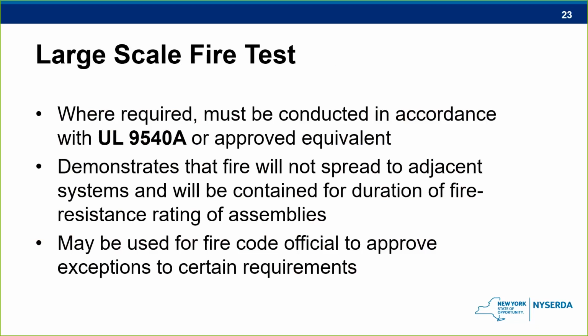On top of that, where required throughout the code, it's kind of sprinkled throughout, large-scale fire testing must be conducted on a representative energy storage system in accordance with UL 9540A, which is really just a testing protocol, or an approved equivalent by an approved testing laboratory. And the point of this test is that it would need to show that a fire involving one system will not propagate to an adjacent system. It should also show that if a fire does occur, it will be contained within the area for the duration of the fire resistance rating of the room assemblies where it's located. That test report would be provided to the fire code official for review and approval. And there are a few requirements throughout the code that can be altered or perhaps made a little bit less stringent based on the results of this large-scale fire testing.